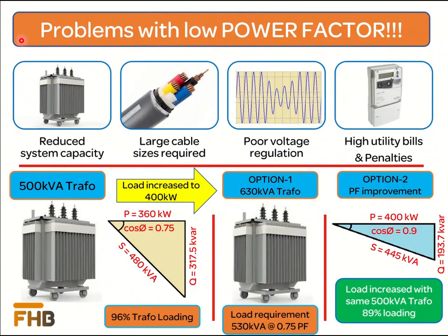The kVA requirement of the system is inversely proportional to the system power factor. Consider a 500 kVA transformer supplying power to a 360 kilowatt connected load at a power factor of 0.75. The kVA requirement is 480 kVA, meaning the transformer operates at 96% loading. If we increase the load to 400 kilowatts at the same power factor of 0.75, the kVA requirement increases to 530 kVA — exceeding the installed capacity of 500 kVA.